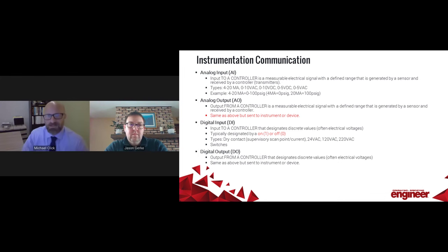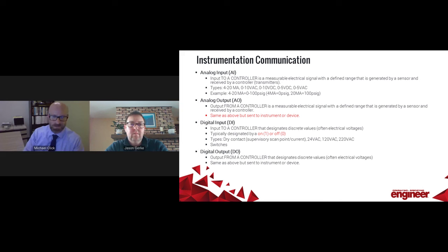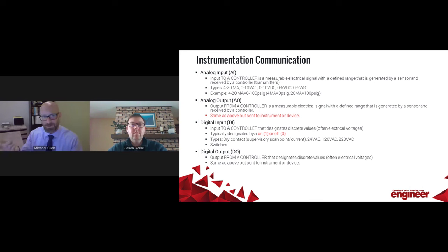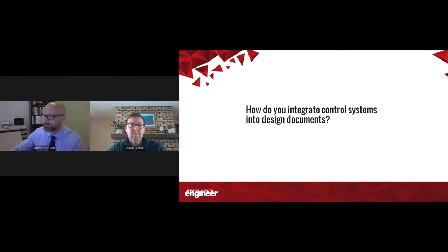It all follows the same process and pattern of input, process, output. Analog systems and digital systems are fairly different. Key words to keep in mind: a pressure transmitter would be an analog input. An analog output is a signal sent across a range to maybe a fan to modulate that fan, damper, or valve. A digital input is discrete — a pressure switch would describe a digital input, anything with 'switch' at the end. A digital output is simply on or off, a one or a zero.